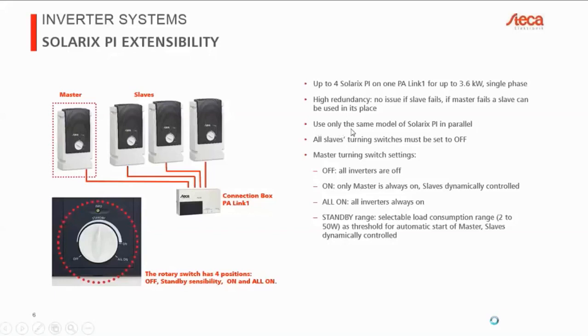This should be obvious, but just to make sure you know, always use only the same model and size of PI inverters together. They should all be identical models. All of the 1 to 3 slaves, so you can use 2 inverters, 3 or 4 inverters. Each one of the slaves must have the turning switches set to the off position.